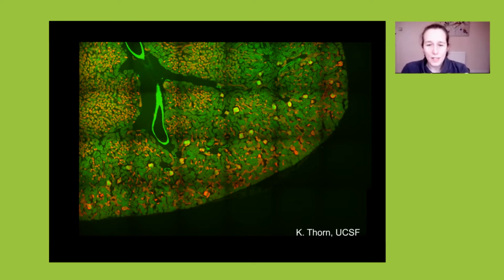Now, this is great because it means that we can see more of the organ than the light microscope can normally accommodate. But what it does mean is we have artifacts. Some of these artifacts are evident. As an example, we have these dark bands that surround each one of these image panes, and this is a consequence of inhomogeneous illumination. You can, to some degree, counter that using flat field correction and so on.